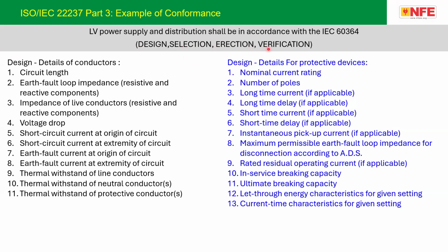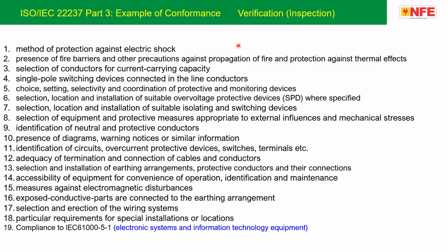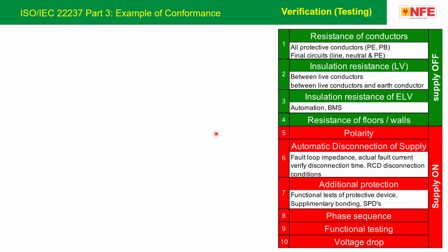This is the sequence. If we look at the verification, which consists of inspection and testing, there are several items to be inspected. You can find this in 60364 part 6 of the standard. Method of protection against electric shock, propagation of fire to be controlled, and there are several other subjects to be inspected.